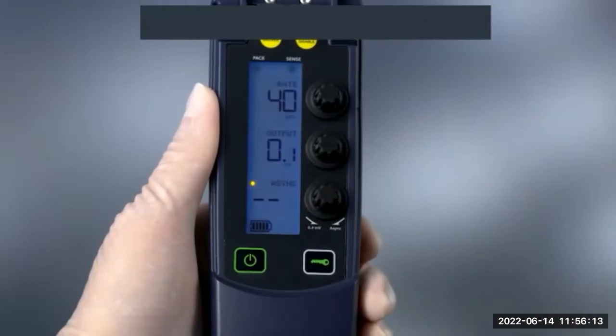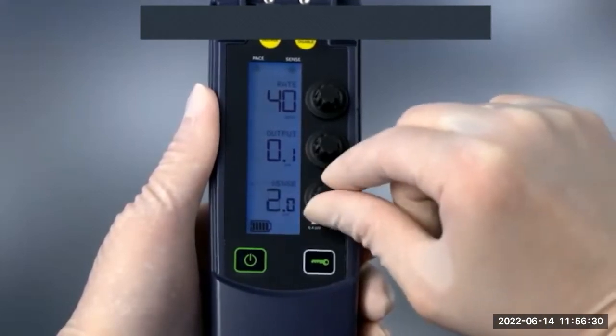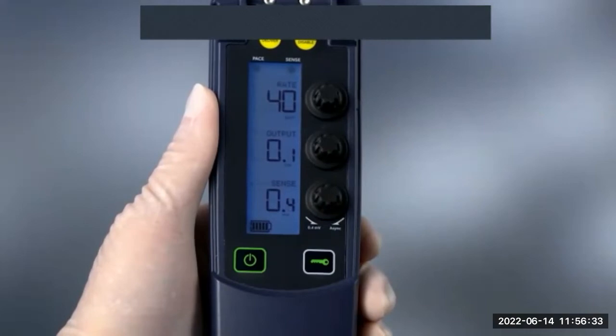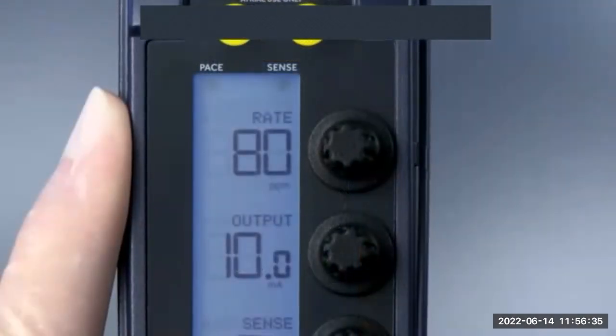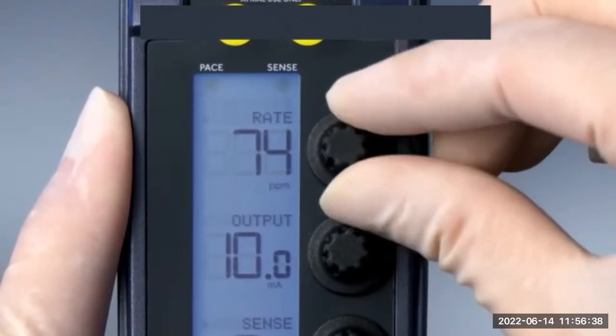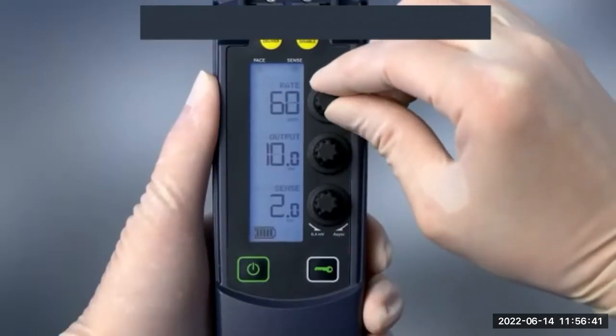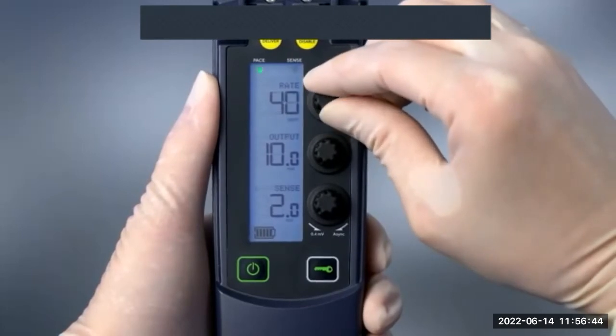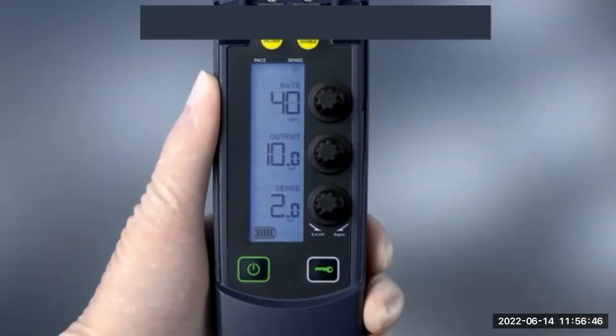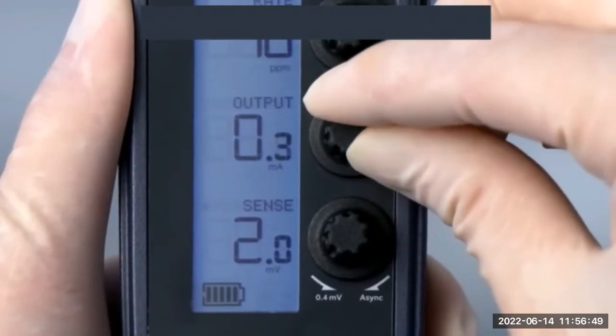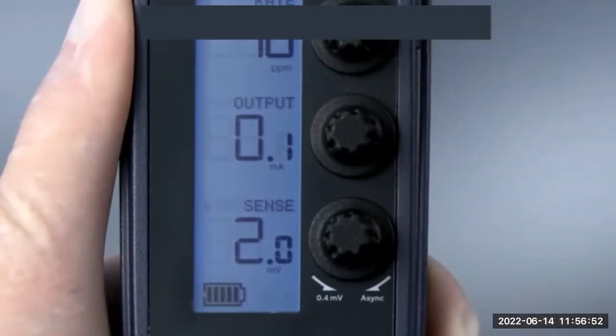When set to async, the sensitivity is set to a value so high that no underlying intrinsic signal can be detected. Therefore, to pace asynchronously, set the sensitivity dial to async. To pace VVI or AAI, the sensitivity setting must be set so the device detects the underlying rhythm. Set the rate to at least 10 ppm under the patient's intrinsic rate. So in this example, we will set the rate to 40 ppm. To reduce the risk of competitive pacing, decrease the output to the minimum value of 0.1 milliamp.